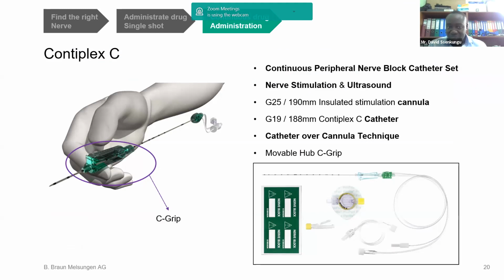So that is the Contiplex C for continuous peripheral nerve block, and it offers you both nerve stimulation and ultrasound. We offer it with a 25 gauge, 190 millimeter insulated stimulation cannula, and the catheter is 19 gauge and 188 millimeter Contiplex catheter. So this is the catheter over cannula technique, because the catheter is already on the cannula. So as you go in to do your block, once you're done with the initial block, you remove the cannula and then you continue with your catheter for the continuous block.